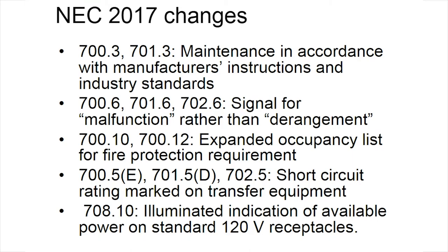And finally, 708 covers critical operations power systems, or COPS. There's a requirement that an illuminated indication show that power is available on standard 120-volt receptacles on standby systems. So that summarizes the changes. Not too much, really. Of these, the most important looks to be the fire protection requirements for emergency feeders, in that they apply to more kinds of facilities.